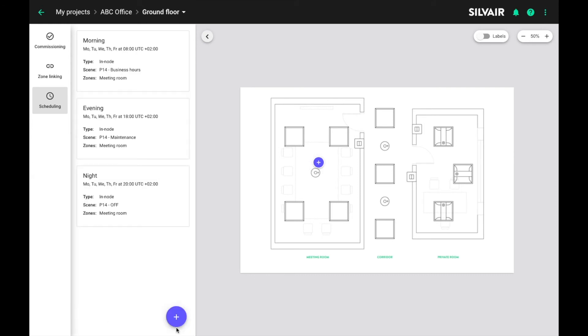Now this was a pretty straightforward example but you can configure up to 16 time events per profile. So this gives you a lot of flexibility in terms of what you can do with these schedules. For example we can have completely different schedules for each day of the week. So now we have the profile, we have the scenes, we have the events. This means we are almost done. The last thing we need to do is upload all these settings into the luminaires.